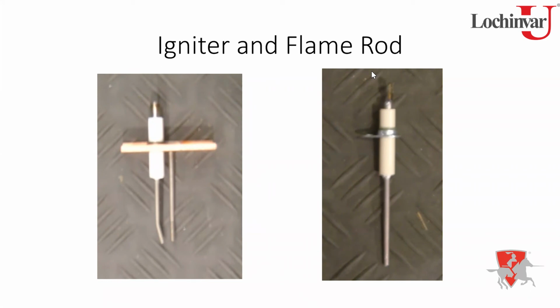Right. And if you want to clean them, whatever you do, don't use sandpaper, right? Why do we not want to use sandpaper, John? Well, that sandpaper could potentially reshape, put grooves in that igniter or that flame sensor. And the one thing about sandpaper is it has the potential to leave a little bit of sand on that rod itself. And whenever you heat up that sand, it forms into glass, which becomes an insulator. So that will mess up your flame signal, and it's just going to sit there and not light. You know, I don't know how often that happens, but it is a possibility.